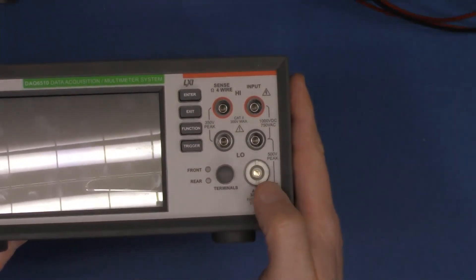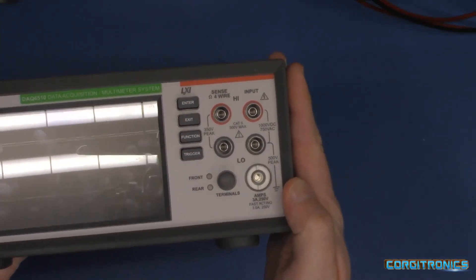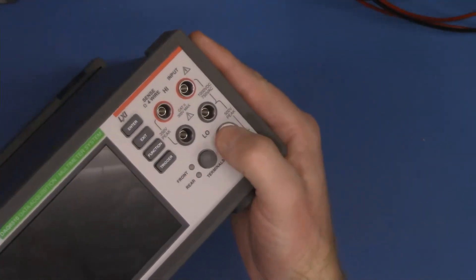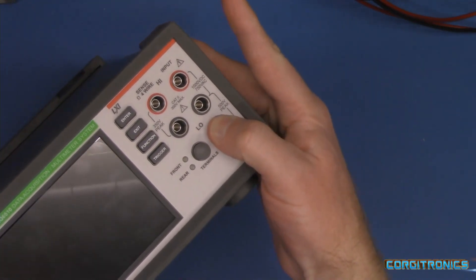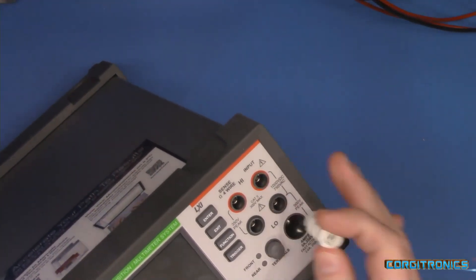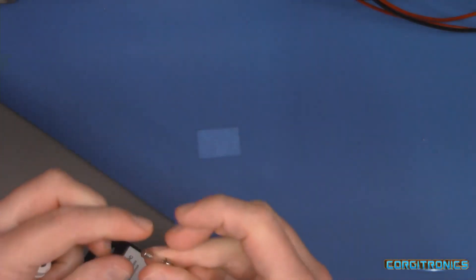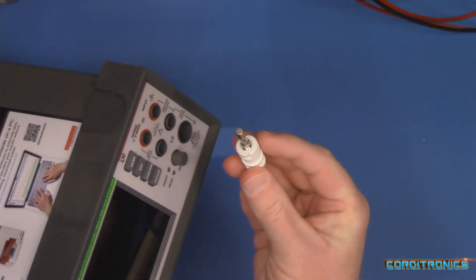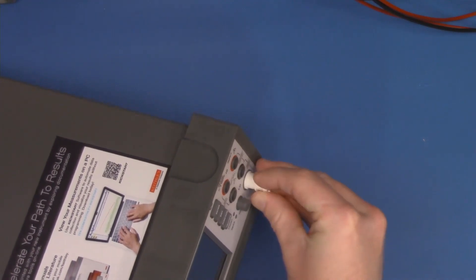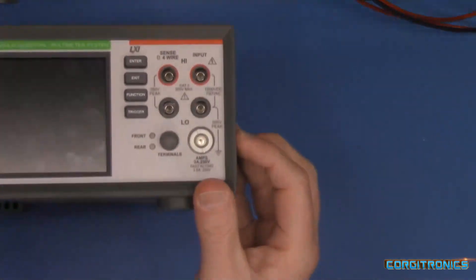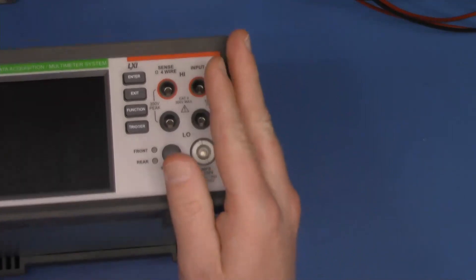And here we have the old school front panel fuse that Keithley had on their older meters for the current range. And all you have to do to replace that fuse, you don't have to take this thing out of your setup and unstack the gear. You just press down on the banana jack there, rotate it and it pops out and you get a little glass fuse. And there's nothing special about this. I think it's a standard three amp, 250 volt fuse. And all you do is slide it into the front panel jack, then slip it in. There we go. And press and rotate and it's back in place. Very handy rather than having to go to the rear panel for me since I have all this stuff racked up.